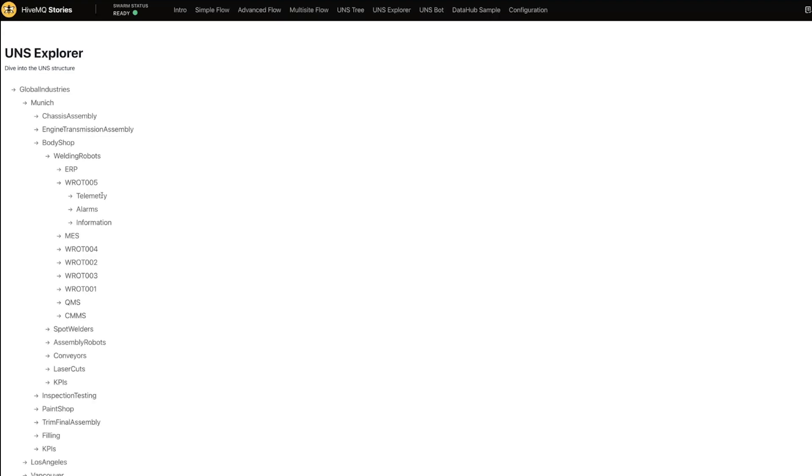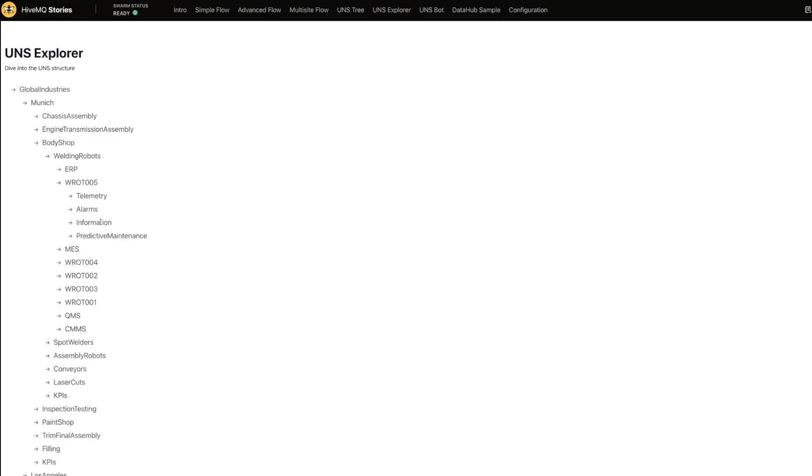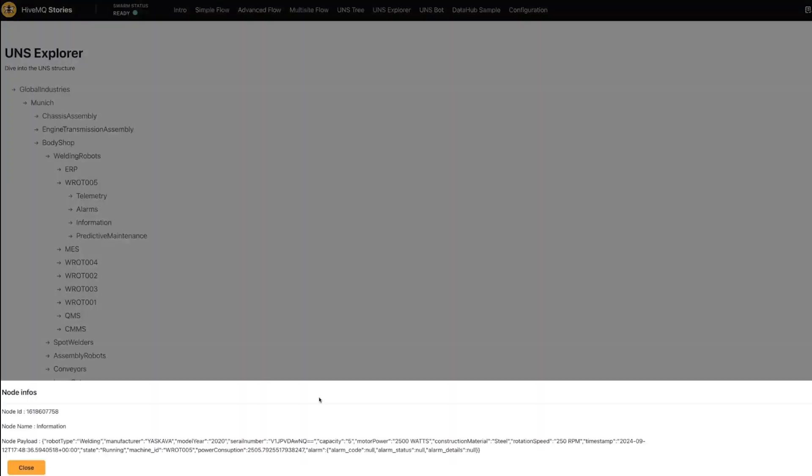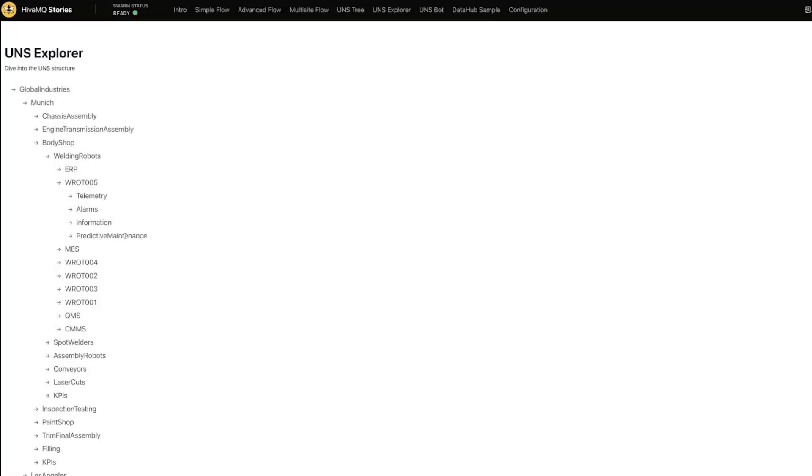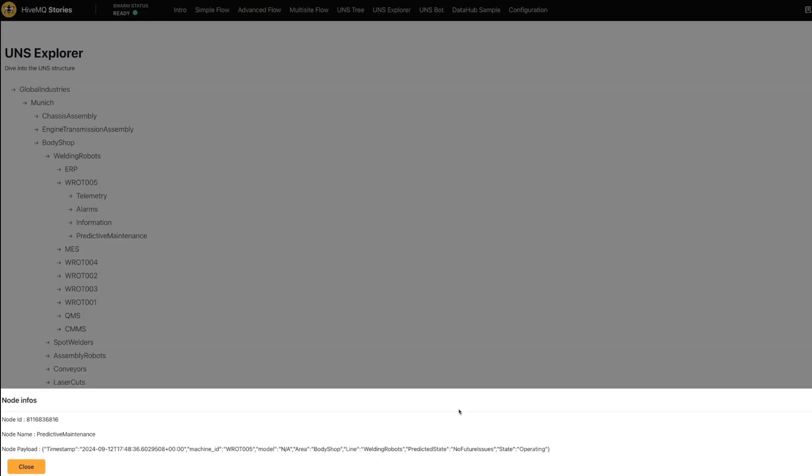I have a set of alarms that allows me to see alarms as they're coming in, and I have an information topic. So this is like an informational namespace that might have information about that specific welding robot, so manufacturer and a serial number and that sort of thing. And then actually this just populated for us, so we have a predictive maintenance which is like a functional namespace. So this is a namespace that is actually providing a specific function and within that predictive maintenance we're making some sort of prediction about how this particular device is operating.